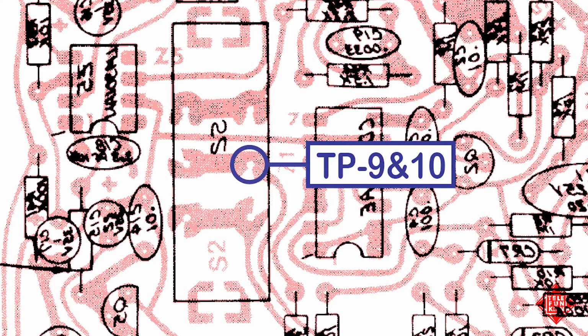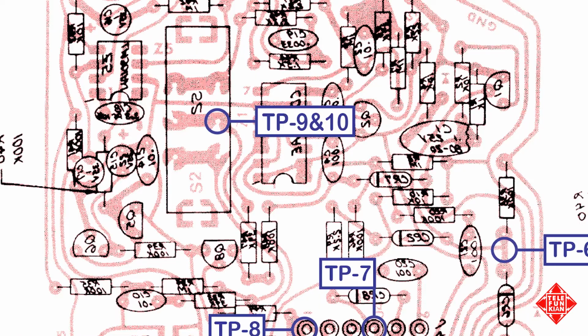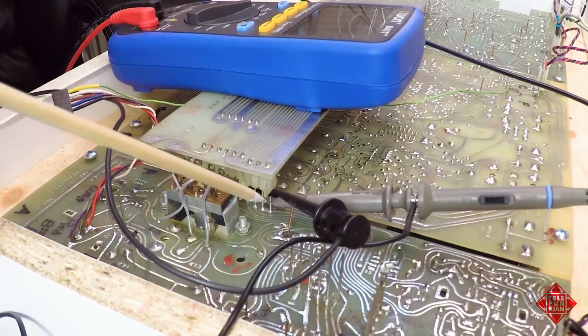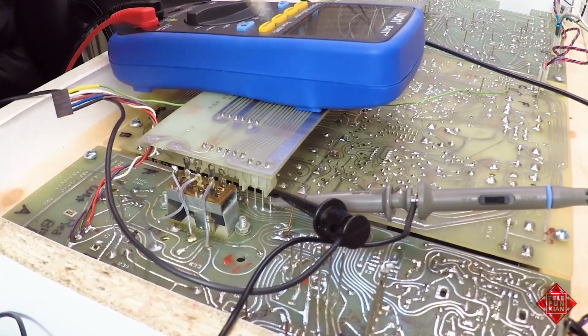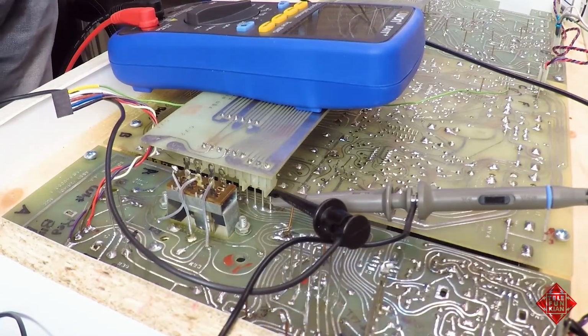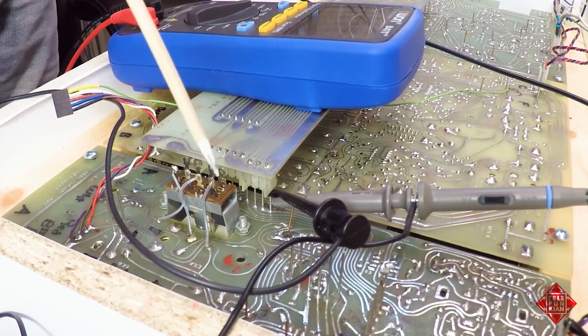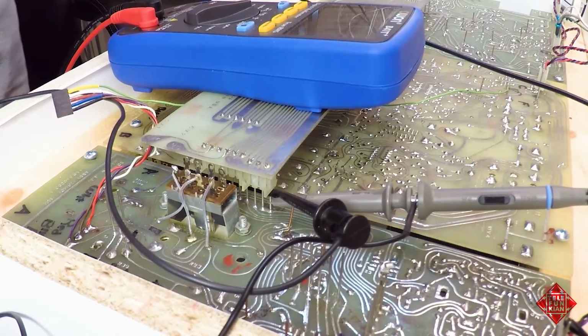The next test point that is on board A is test point 9, and that is the white noise test point. Both test point 9 and test point 10 are the pin number 1 that is on the interconnect PCB that connects PCB A, B, and C together. The noise signal moves from board A through the rest of the instrument.